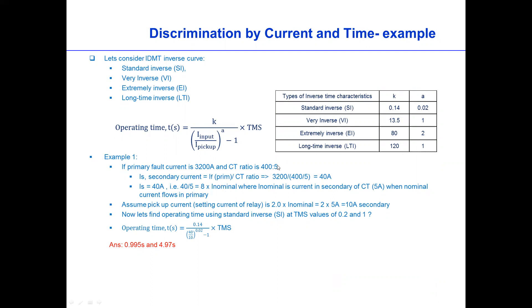Then if the pickup current is 2 times nominal current, which is 2 times 5 amp, which is 10 amp, we can find the operating time using a standard curve, for example, when the TMS value of 0.2 and 1 is provided.